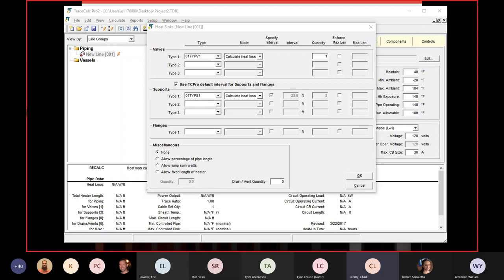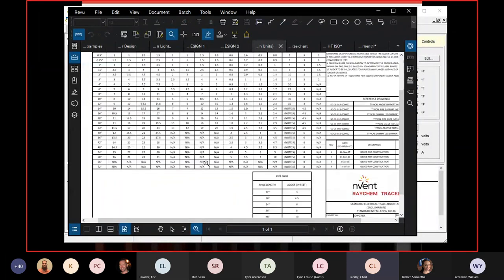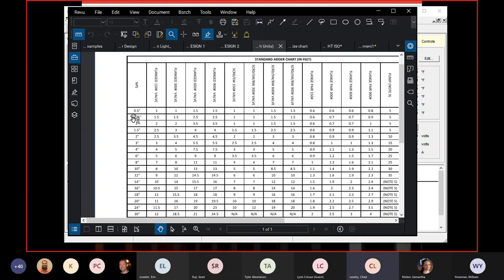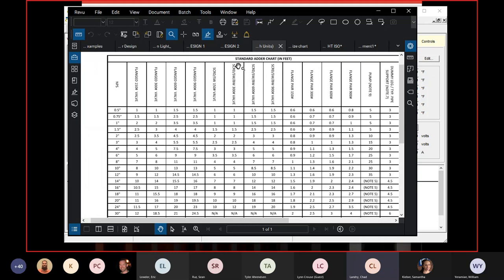Here's our standard adder chart, which shows how much cable to add per heat sink based on pipe size. For an 8-inch pipe with a flanged valve (150-pound rated), we add an extra 7 feet of cable because it's a heat sink — we lose extra heat at that point. The field guys use this as a rule of thumb during installation. Our particular example showed two valves and five pipe supports.